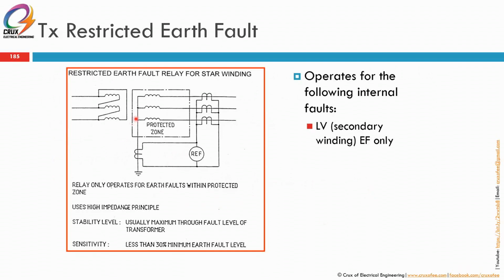Okay, let's see here. Restricted earth fault. So here's on our left side, here is the primary winding, the LV secondary winding. So relay will only operate for a fault within the protected zone lah. So in this case, we are looking at the protected zone is between two CTs. So the first CT is the one located at the neutral star point. The second CT, which is measuring a fault by summation.